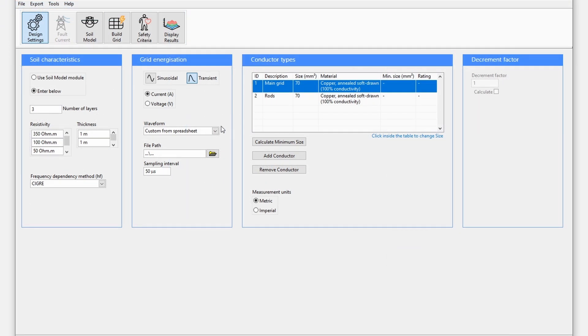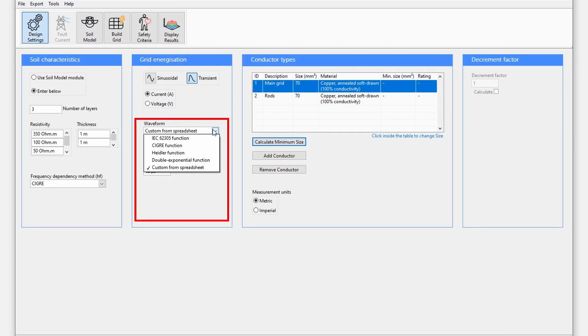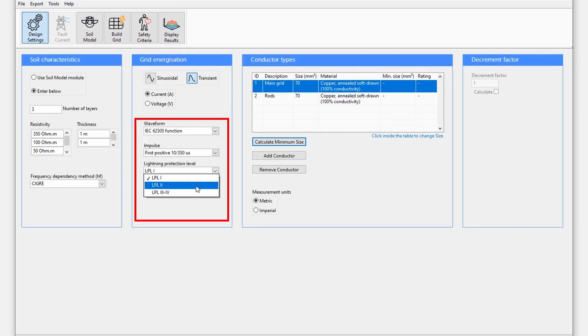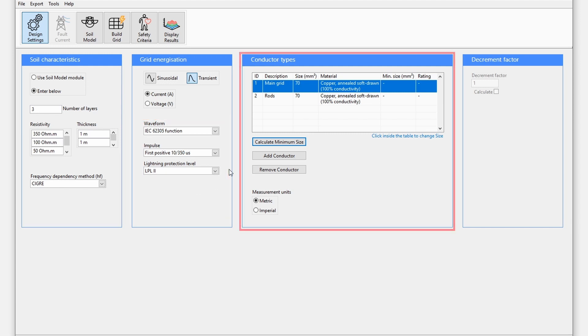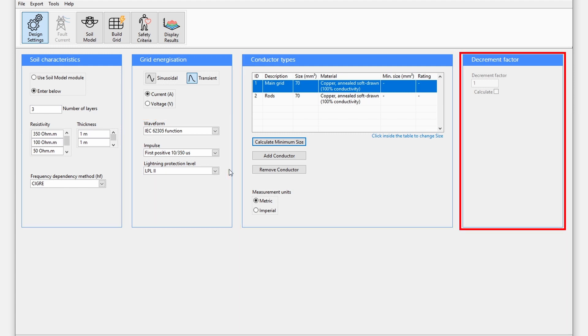In this tutorial, we will use an IEC function, first positive impulse, with lightning protection level 2. The conductor type section remains the same, and the decrement factor is disabled since it is not applicable for transient waveforms.